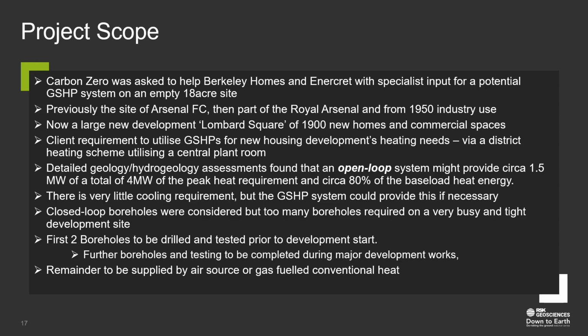The client wanted to reduce their carbon impact. This was the first time they tried a ground source system on a scheme of this size, and they wanted to do it via a district heating scheme. There are a couple of options, an ambient loop or a central plant, and their plan was to use a central heating plant, with a large plant room with heat pumps distributing heat around the housing development. Before any of this happened, we had to do a site-specific assessment of the geology and hydrogeology of the site.